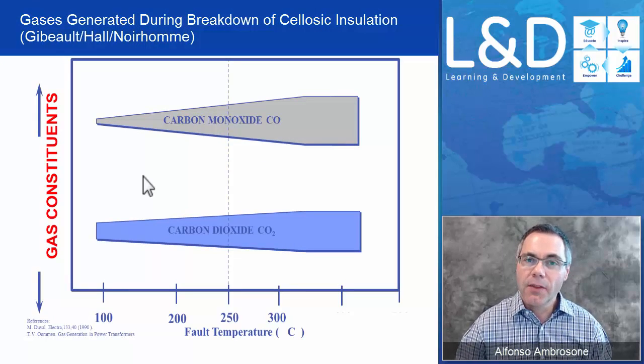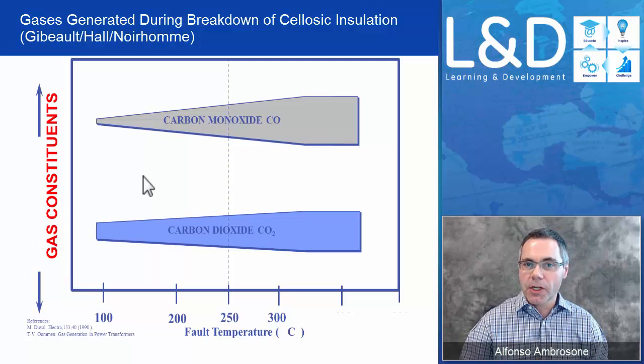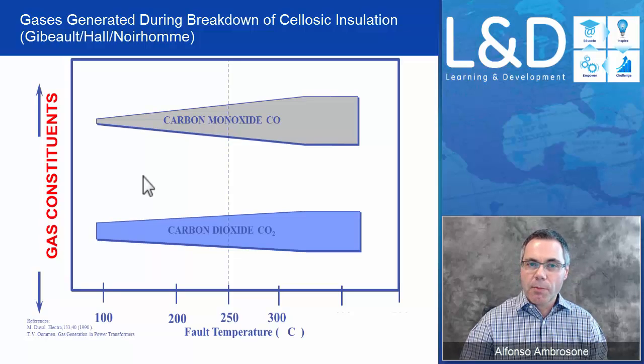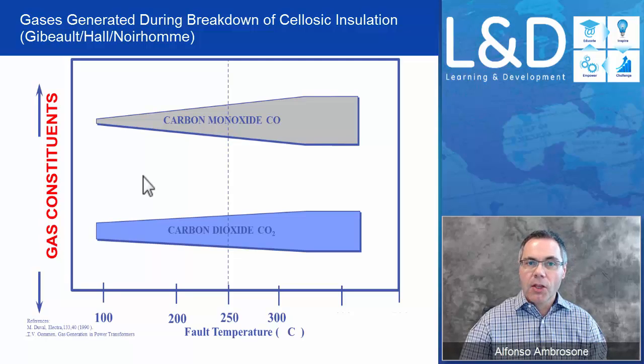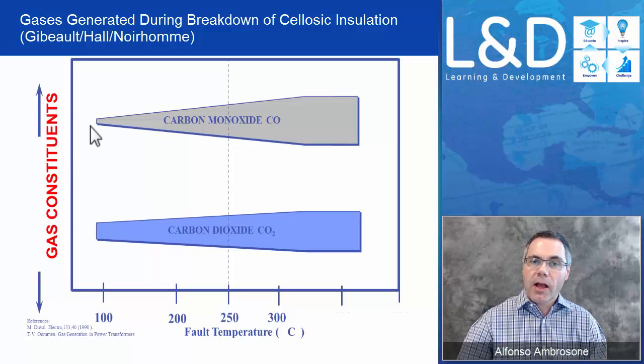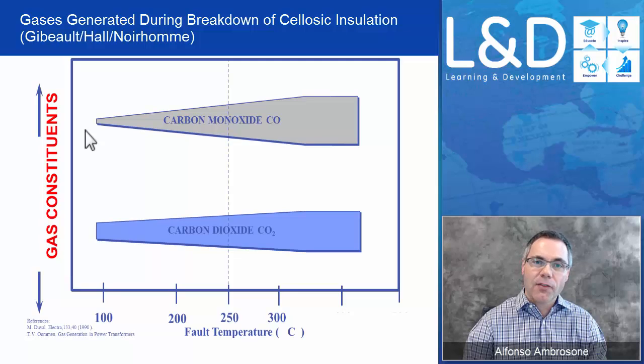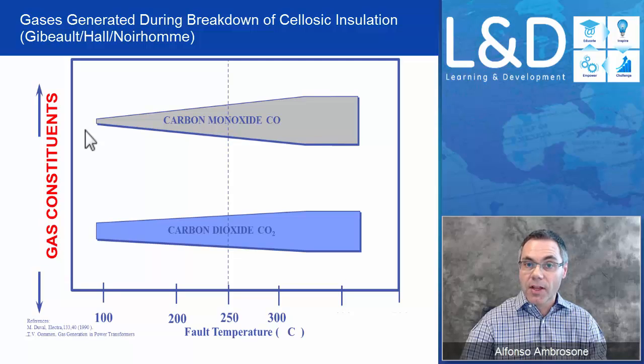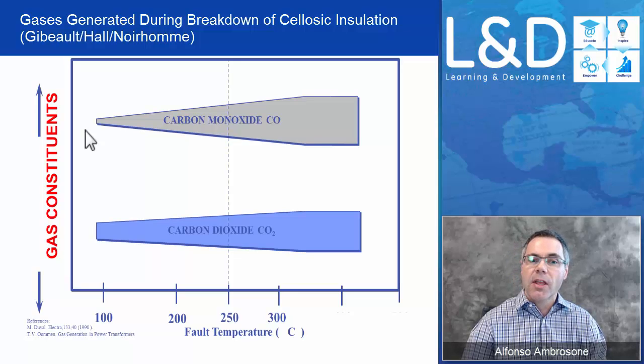Here's a breakdown of CO and CO2 in relation to temperature. It does not take a lot of temperature to start breaking down the paper. Depending on the type of paper, they all have a rated hotspot, which usually runs between 95 to 110 degrees Celsius. Anything below 95 degrees will not too greatly affect the paper, but anything above 95 degrees Celsius will start generating paper degradation and produce gases. The predominant gases here are CO, CO2, and moisture.